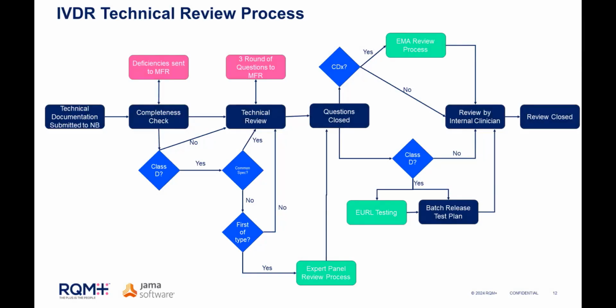When we break down that technical review into a little bit more detail, this is what it looks like. So you submit the documentation to the notified body. Most notified bodies do what's called a completeness check, where they just look at what you've submitted and make sure they have all the documents they need, sort out any deficiencies. If it's a Class D device, you'll need to make sure that you're meeting certain requirements for those. So mainly, have you met common specifications, or is it a first of type Class D without common specs? So then we'll get into tech review. That will go through 3 rounds of questions typically for most notified bodies, where you'll be able to resolve deficiencies in your technical file. That'll go back and forth. While that's happening, if you do have a Class D, that first of type expert panel review process will be ongoing.